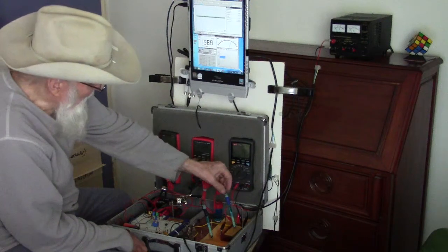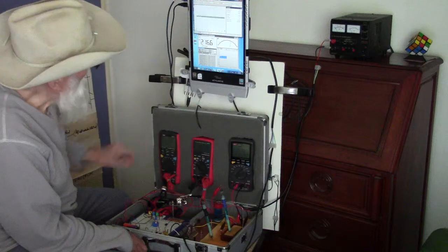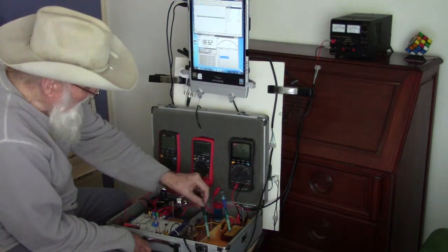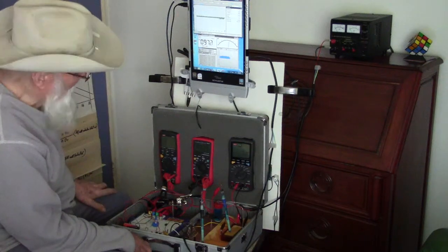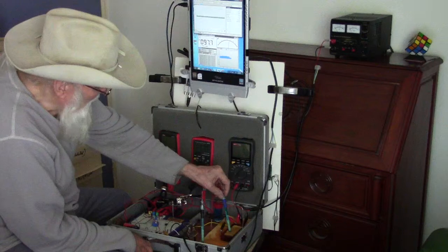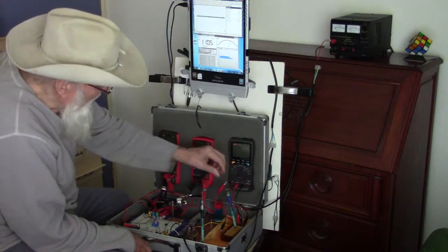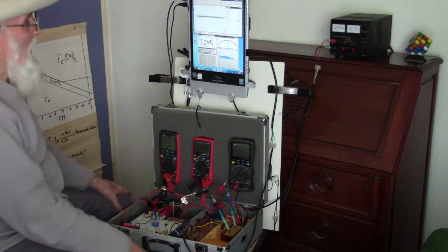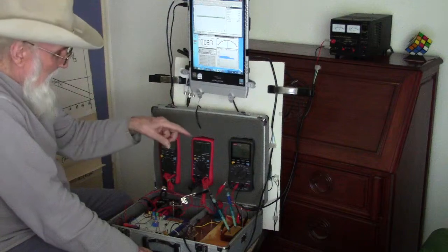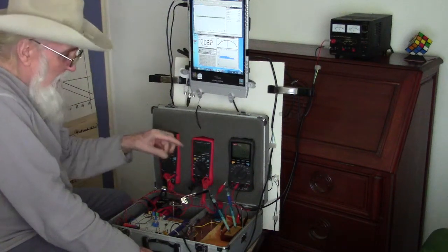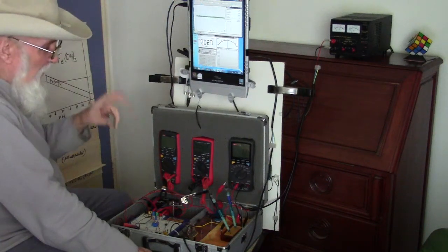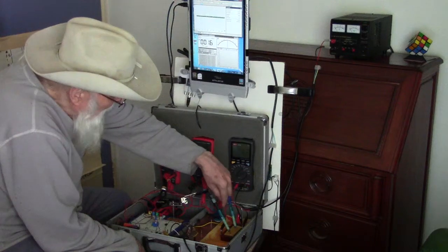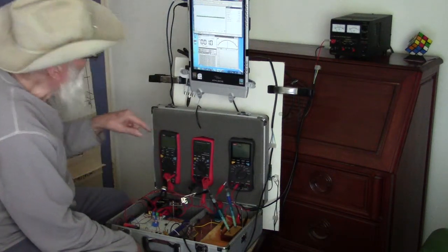So from the cathode to the anode, there has been a shift which is recorded here, and if I move this, there is yet another shift, and if I swap, if I put this over the cathode and this on the anode, exactly replicating the requirements of DIN 50918, where the electrode must be close to or at the interface between the electrolyte and the anode of the corrosion cell.